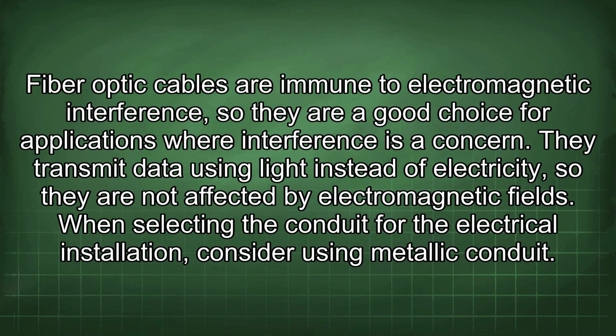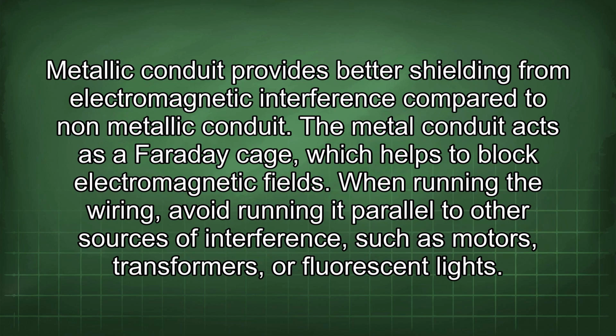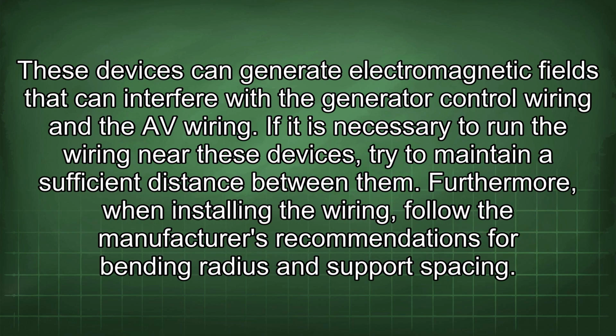When selecting the conduit for the electrical installation, consider using metallic conduit. Metallic conduit provides better shielding from electromagnetic interference compared to non-metallic conduit. The metal conduit acts as a Faraday cage, which helps to block electromagnetic fields. When running the wiring, avoid running it parallel to other sources of interference such as motors, transformers, or fluorescent lights. These devices can generate electromagnetic fields that can interfere with the generator control wiring and the AV wiring. If it is necessary to run the wiring near these devices, try to maintain a sufficient distance between them.